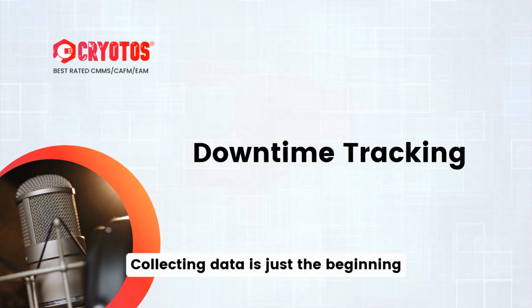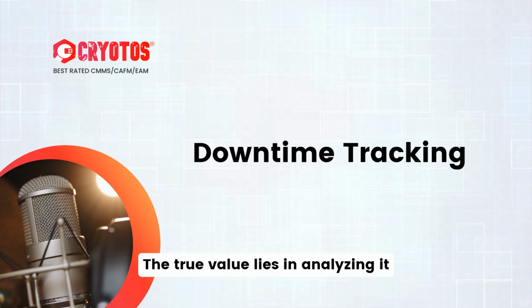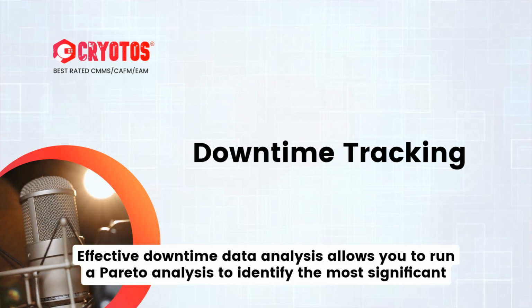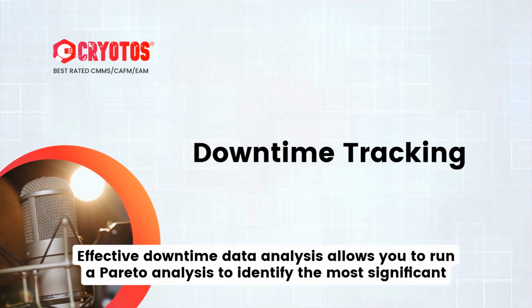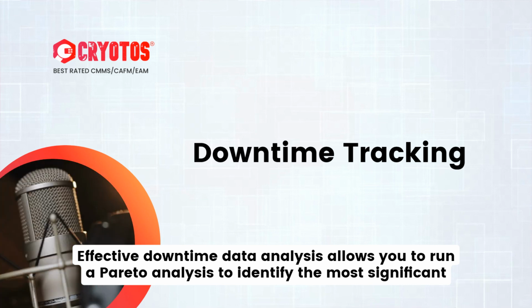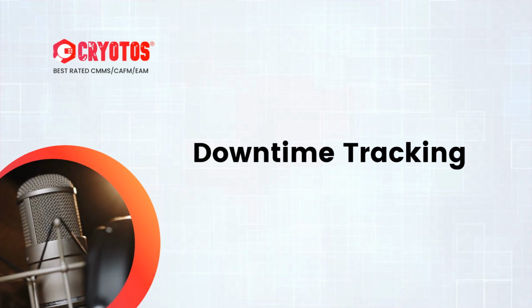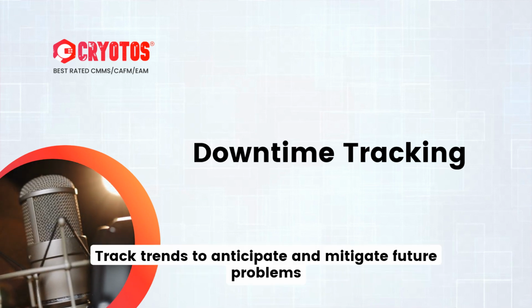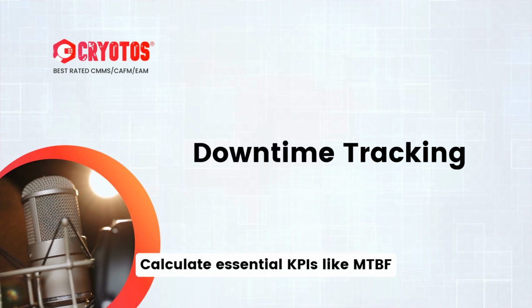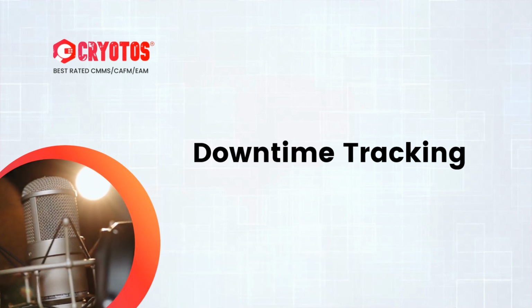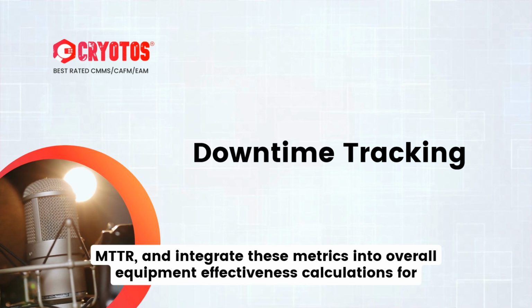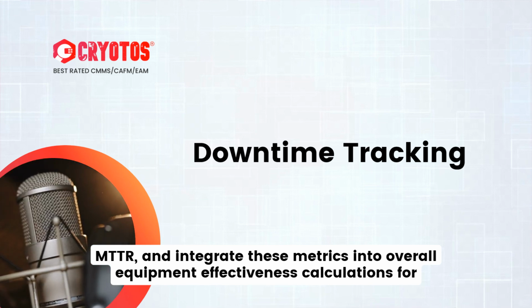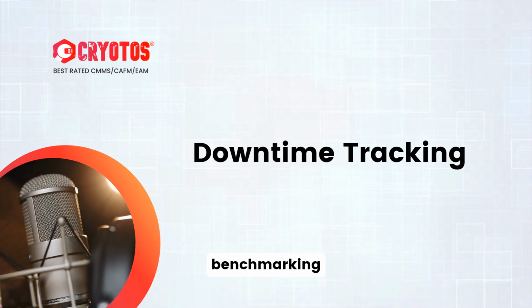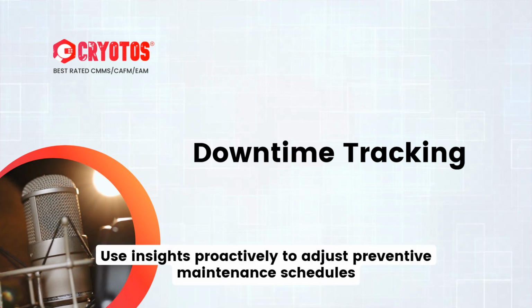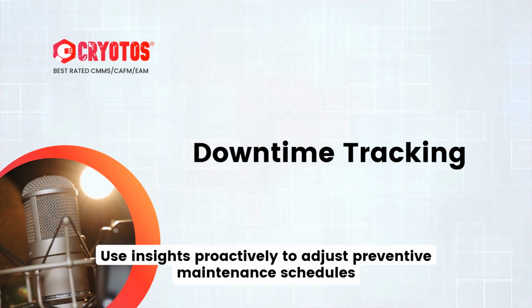Collecting data is just the beginning. The true value lies in analyzing it. Effective downtime data analysis allows you to run a Pareto analysis to identify the most significant issues, track trends to anticipate and mitigate future problems, calculate essential KPIs like MTBF, MTTR, and integrate these metrics into overall equipment effectiveness calculations for benchmarking. Use insights proactively to adjust preventive maintenance schedules.